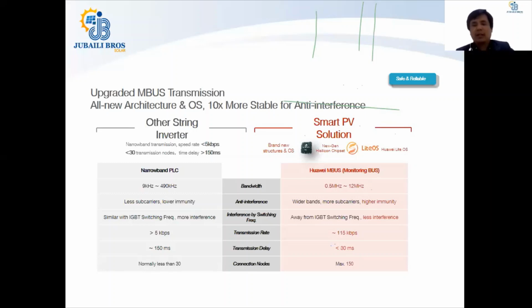to damages. The M-bus communication is very fast, and the bandwidth is from 0.5 megahertz up to 12 megahertz compared to the narrowband PLC, which is 9 kilohertz to 490 kilohertz. The transmission rate has thus increased, and the transmission delay has decreased, which gives you much benefit in terms of using an M-bus with the new range of Huawei inverters.